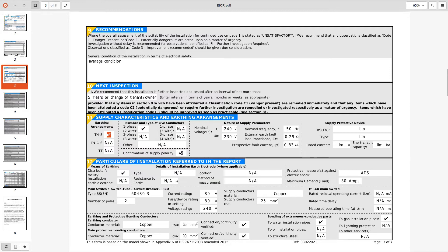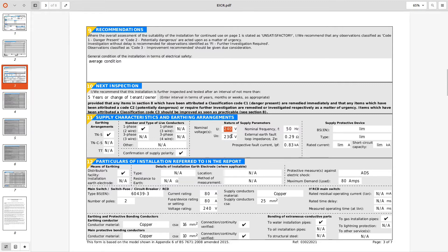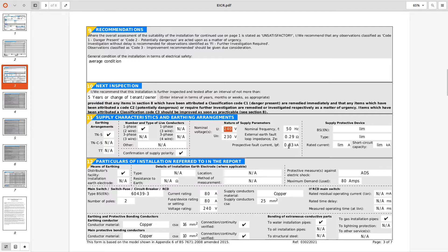Single phase polarity was okay. Nominal voltages, U voltages line to work, sorry line to line, so that should have been 400 presumably if there was a three phase supply in use. So it's only a single phase because we've ticked single phase, so that should have just left a line through it or not applicable. And U nought is line to earth 230 volts 50 hertz.